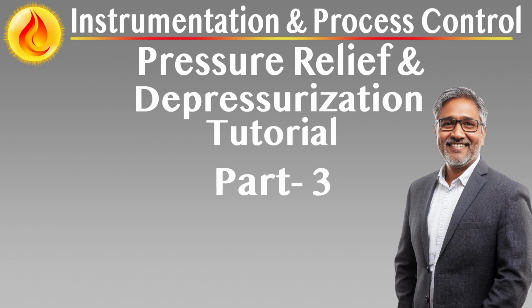In some systems, especially those with slow warm-up behavior and normal operating pressure well below design, sizing may instead ensure that pressure does not reach 50% of design pressure within 30 minutes. For rotating equipment, faster depressurization may be needed to avoid seal oil system failure. The required time should be confirmed with the equipment vendor. Key parameters for depressurization calculations.